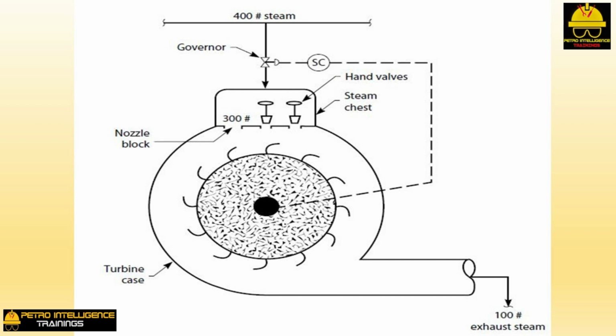If we close off one of the two horsepower valves, steam flow into the turbine will drop, initially by 20%. The turbine will slow. This will cause the governor valve to open. The pressure drop across the governor will decrease. The pressure in the steam chest will rise. The flow of steam through the 60% port nozzle and the remaining 20% port nozzle will increase.